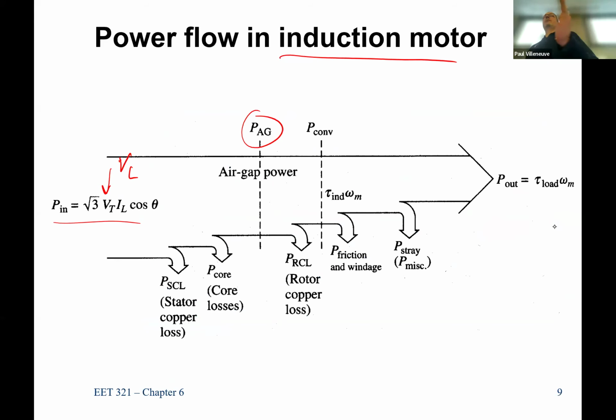Now, all the power that needs to go for the electrical system, or to make it work electrically, is done. We don't have any more losses in electric power. All the losses moving forward are a result of mechanical. So why not call this power our converted power? That's the power that has been converted from electrical to mechanical. And here, because it's mechanical power, we can write it as a function of torque, because mechanical engineering folks don't really care about power, especially from a rotating machines perspective. They really care about torque. So this is the induced torque times omega sub m, the speed of operation.